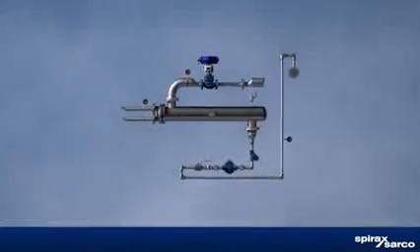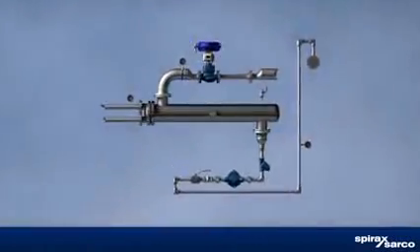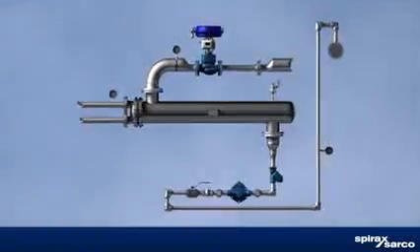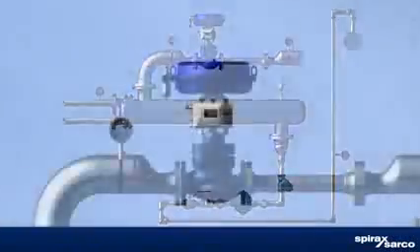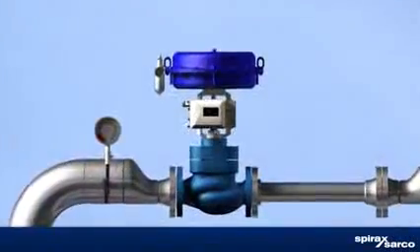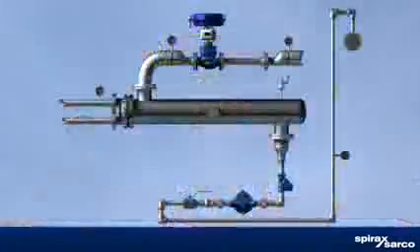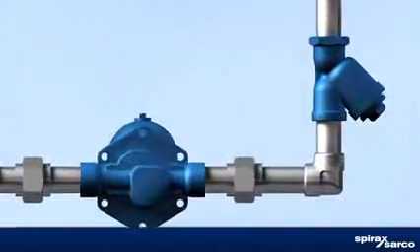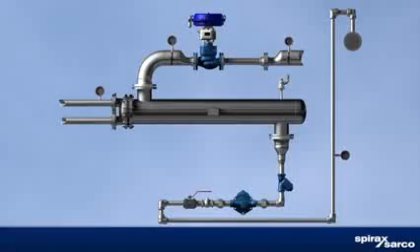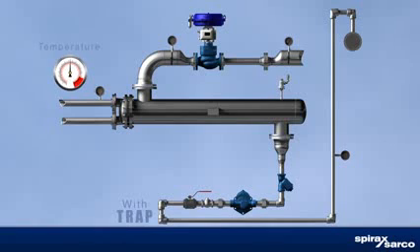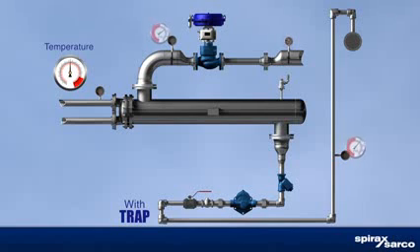The most common process heating heat exchanger hookup involves a temperature control valve on the steam line to the heat exchanger and a steam trap on the condensate line from the heat exchanger. The shell side is the steam space. A control sensor signal at the tube side outlet is used to throttle the steam control valve to maintain set point temperature.